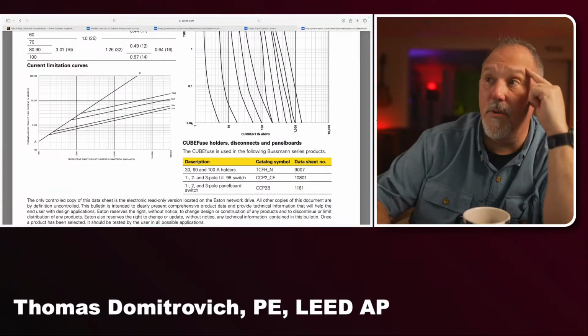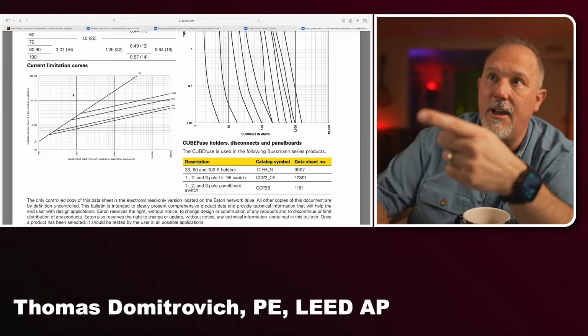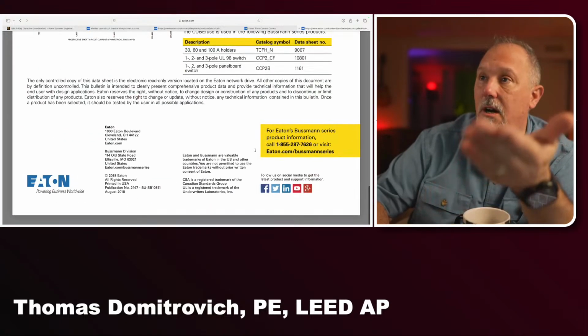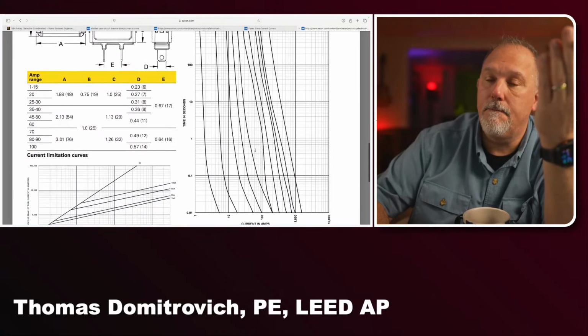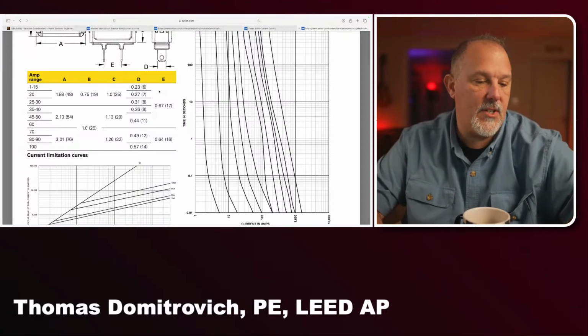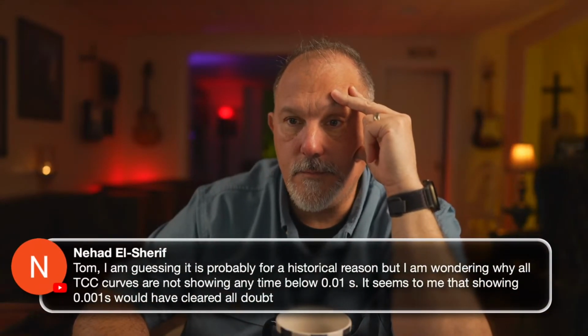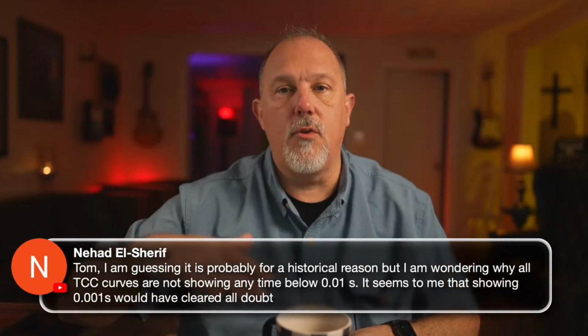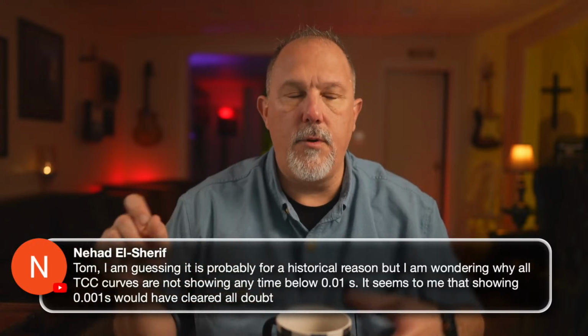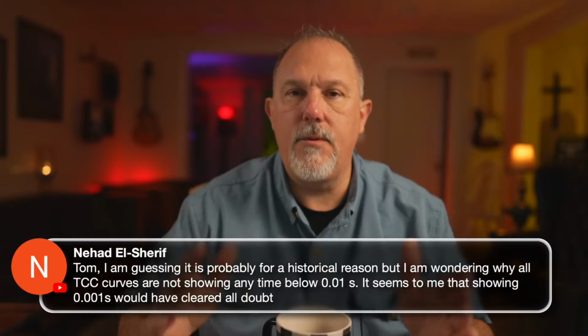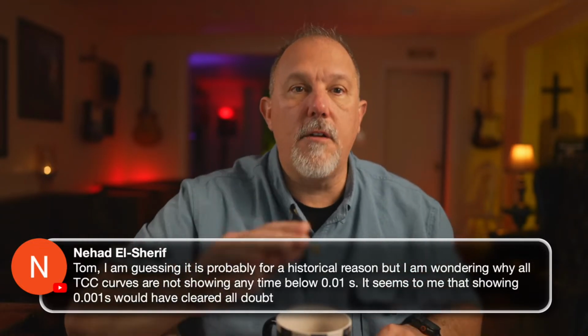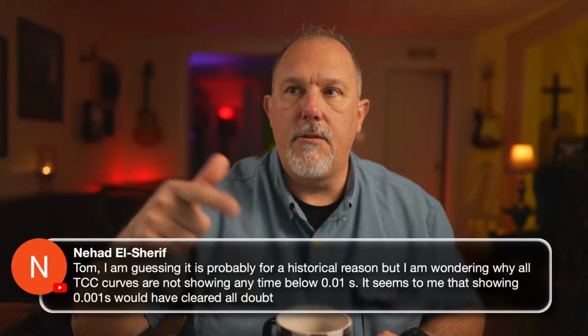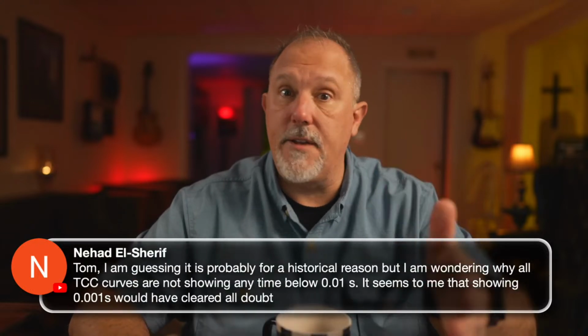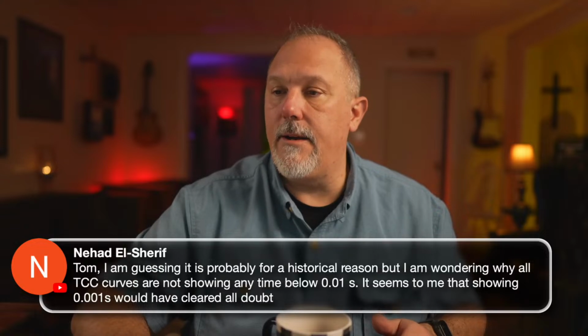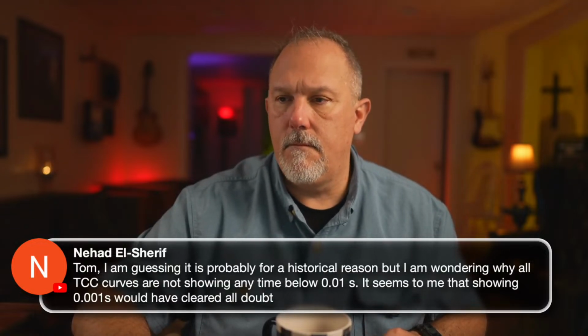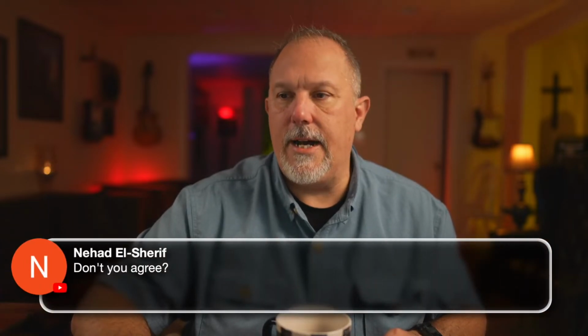And I know why they don't show below 0.01 seconds, because now we're getting into the current limiting region and we use our current limitation curves. All of the fuses are current limiting in nature, so they're not going to have that. So Nihad, I would agree with you. If we showed more information, it would smack you in the face. I would 100% agree that it would be hard for an engineer or anybody to say something either does or does not selectively coordinate because it is on the TCC curve. So I don't disagree with you. Don't you agree? I agree.